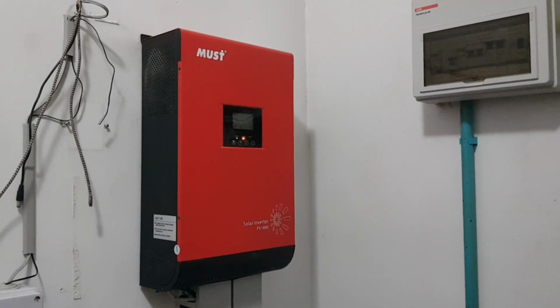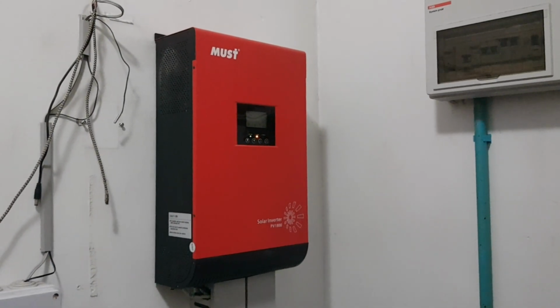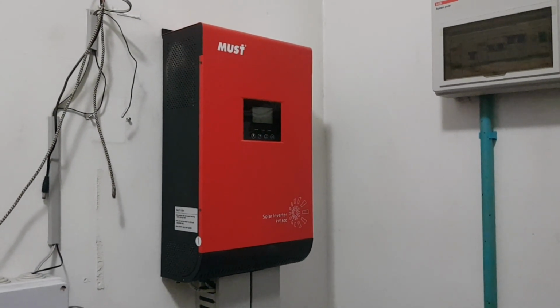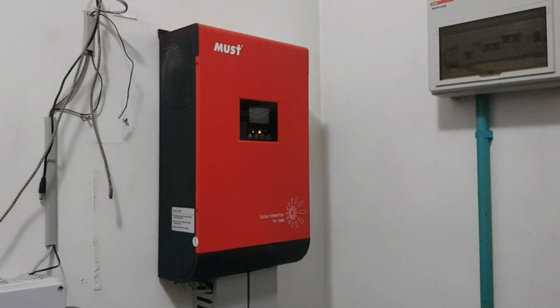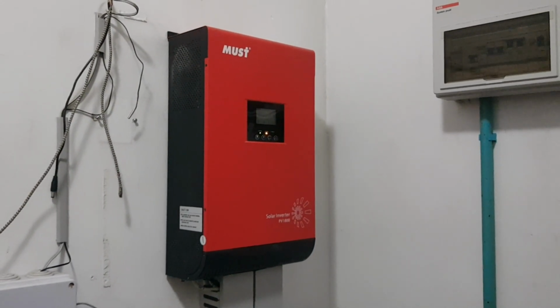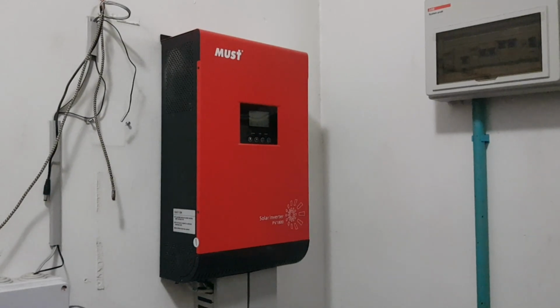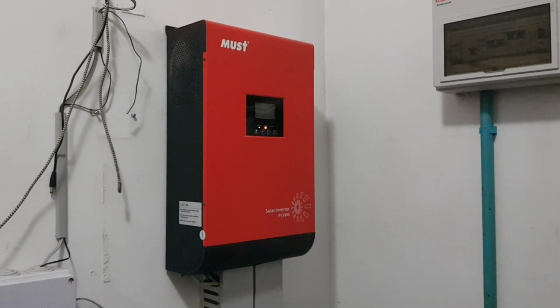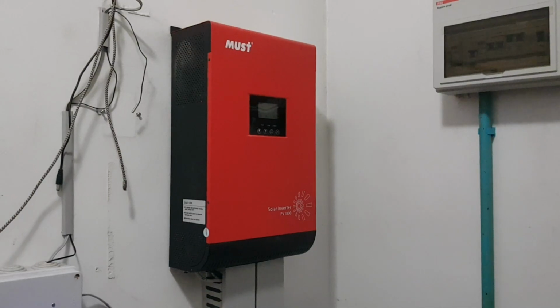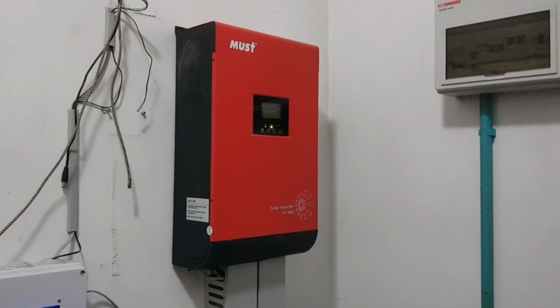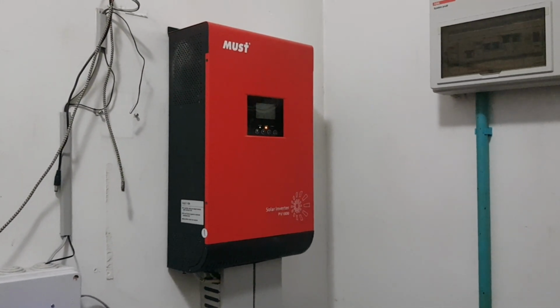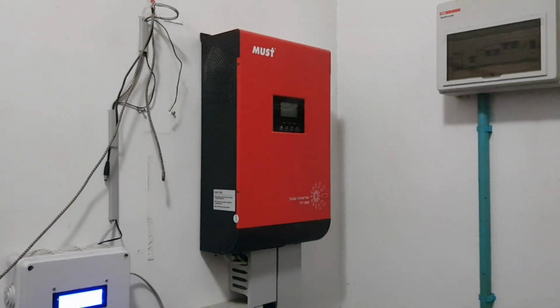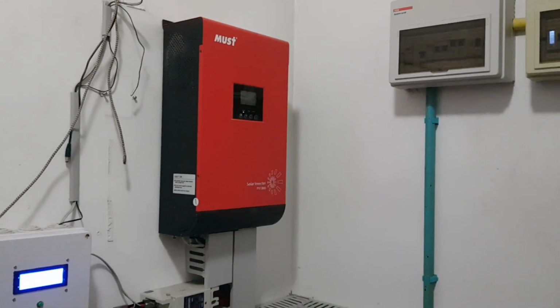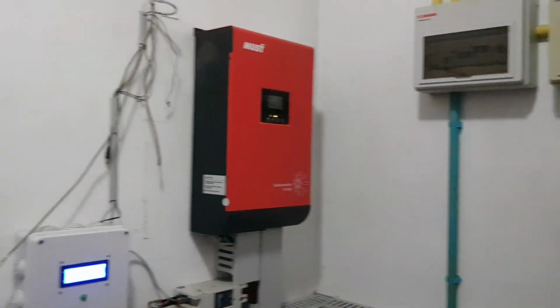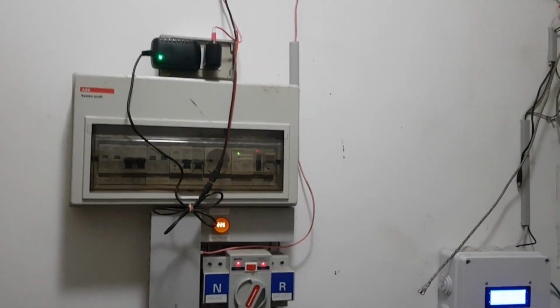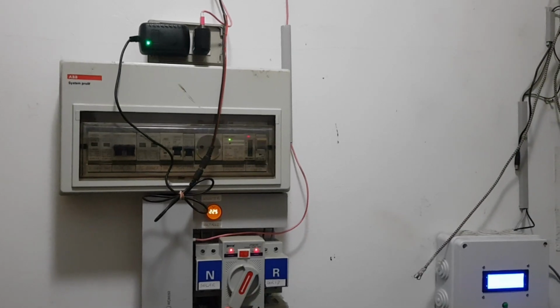So the dry contact would equal an off-grid, on-grid relay contact. This is typically only in the solar priority mode. So where solar and battery are available, it will be off-grid, and when the battery is depleted and solar is not available, it will then switch over to the grid. This information can then be taken from the dry contact and used to create a neutral to ground bond, which will be somewhere in your distribution then.